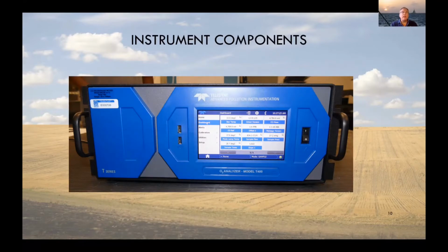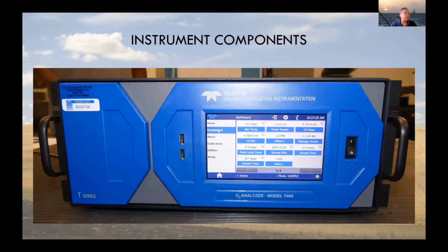So we're going to talk about instrument components. This is the front of a Model T400 Teledyne ozone analyzer. One of the important things to note here is that you can view on the dashboard a number of the test points, and these are some of the critical parameters that need to be monitored in an ozone instrument to assure that it's working properly.